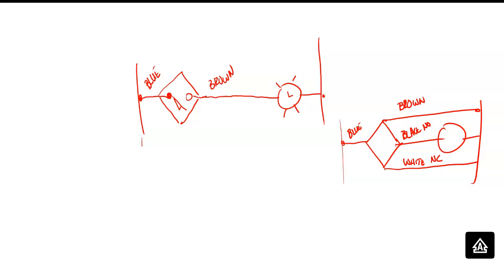But most of these sensors now are operating on lower voltage. And what's the problem with 120 volts? So why are most control circuits like 24 volts AC or around 24 volts DC? That's exactly right. Because NFPA 70E specifies that anything above 50 volts is considered a lethal voltage. And that means we're going to have to start wearing what? Additional PPE, right?